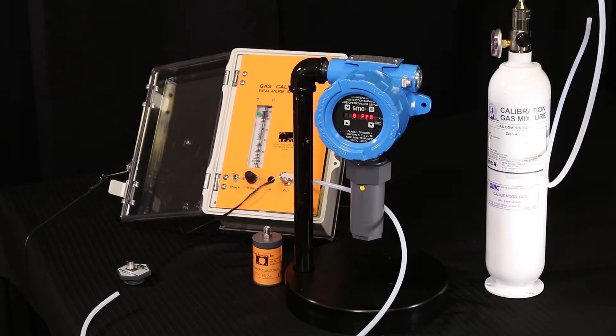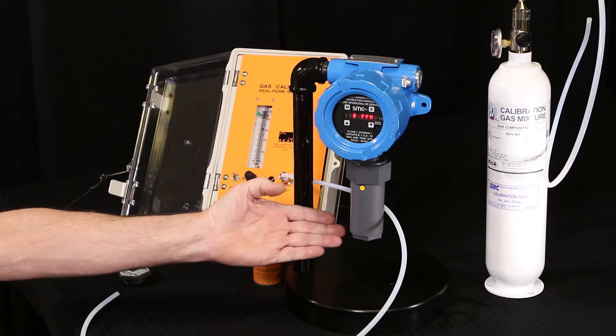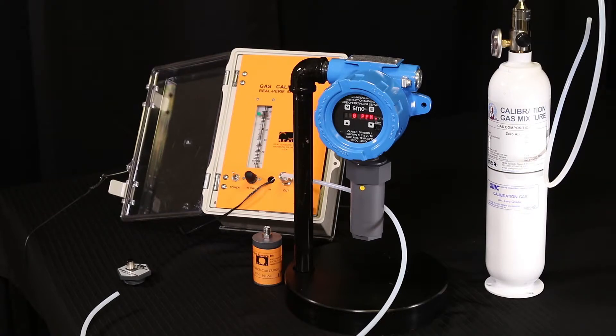Once calibration is complete, turn off the pump and disconnect the perm tube from the T. Be sure to restore the perm tube with the scrubber cap. Reinstall the gas detector into service and allow at least one hour for it to stabilize before beginning the calibration process.